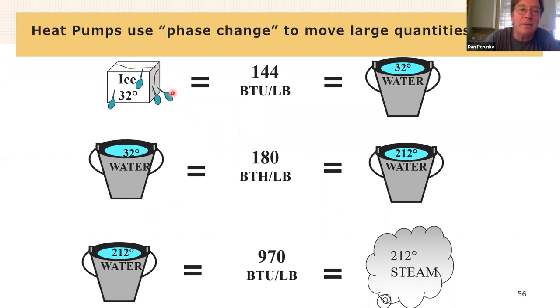So ice is at 32 degrees Fahrenheit at sea level or colder, right? And then water that is about to freeze is also at 32 degrees Fahrenheit. And so the difference between 32 degree water and 32 degree ice is that you have to remove 144 BTUs per pound of the material. So the variable that we're comparing that to is how much energy it takes to change the temperature of the water, right? So if we had 32 degree water and we wanted to get it to the point where it boils, we would have to add 180 BTUs per pound of water to get from 32 to 212.